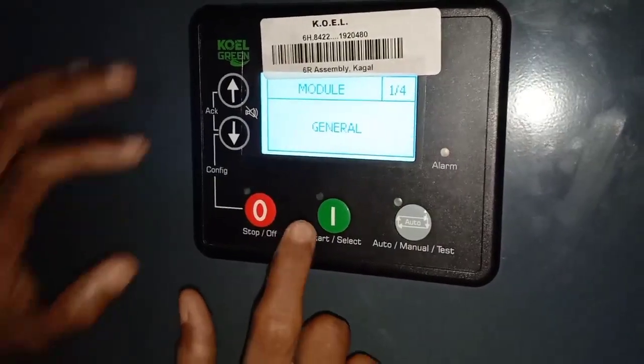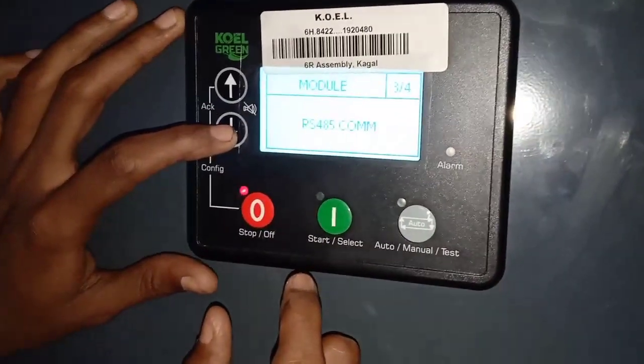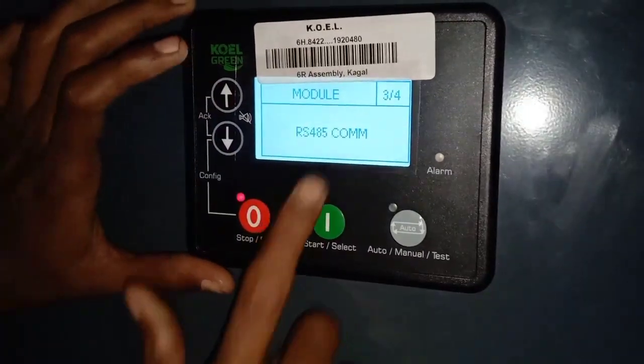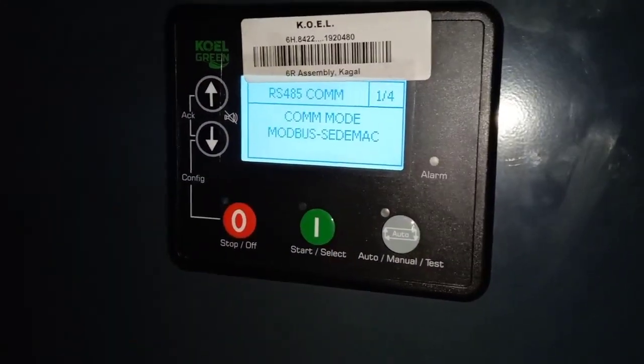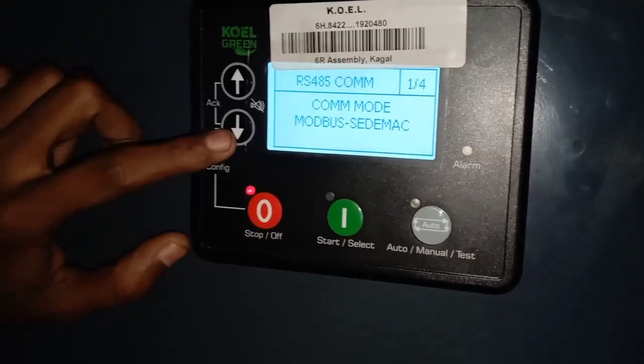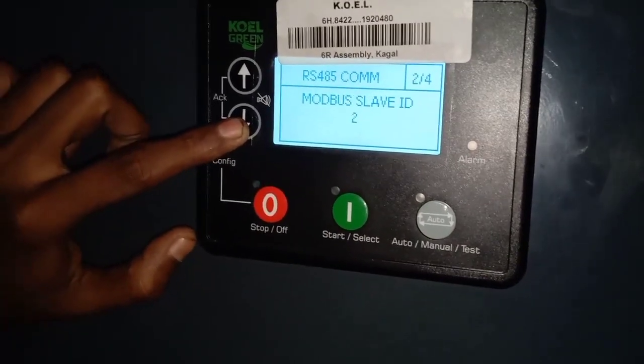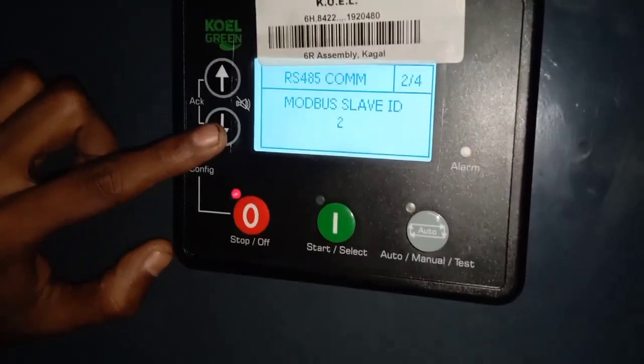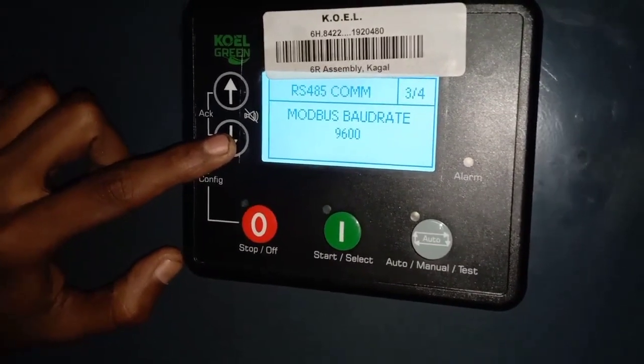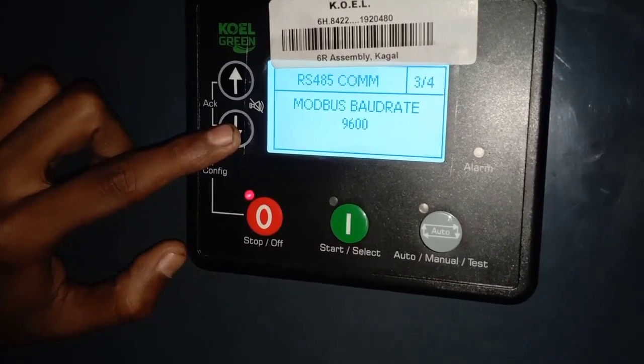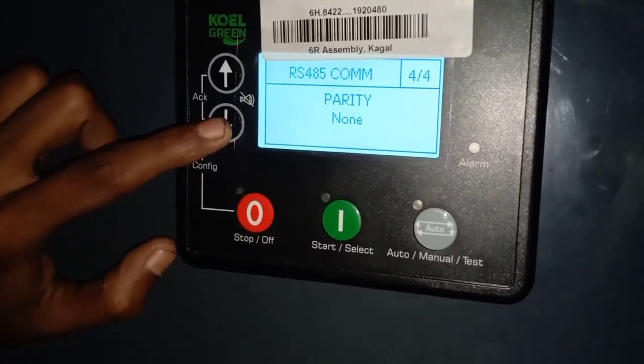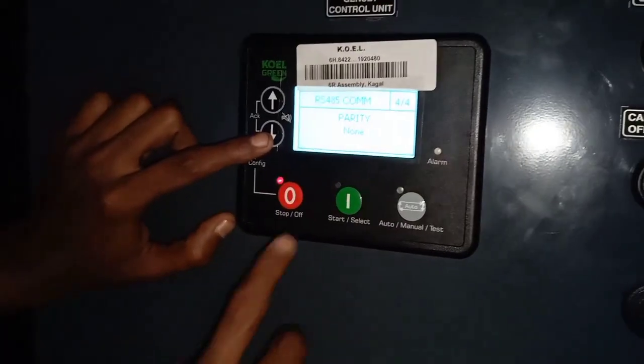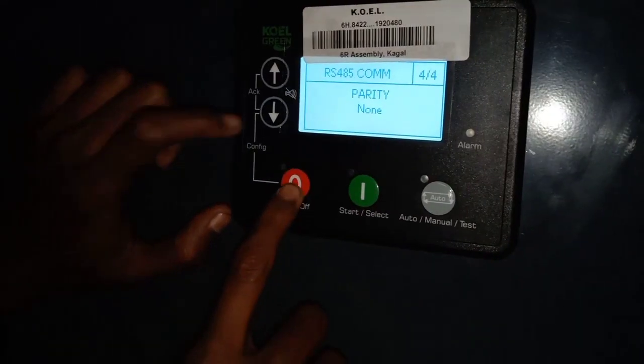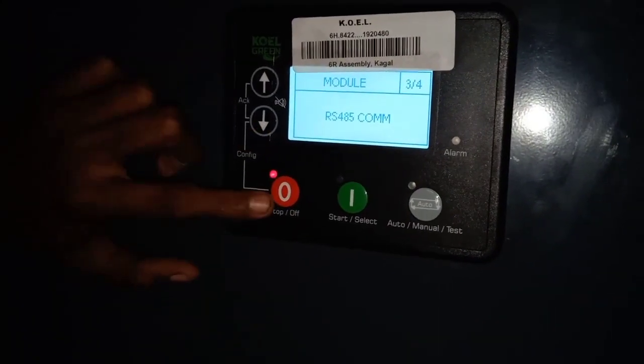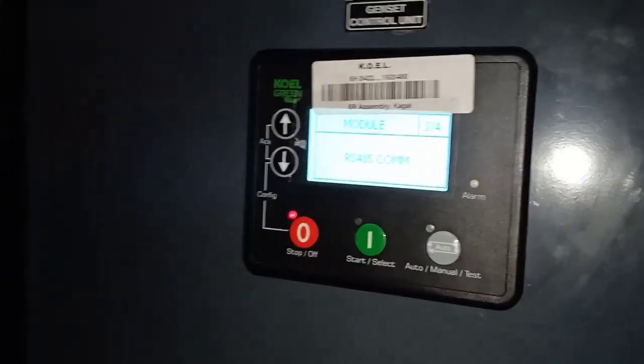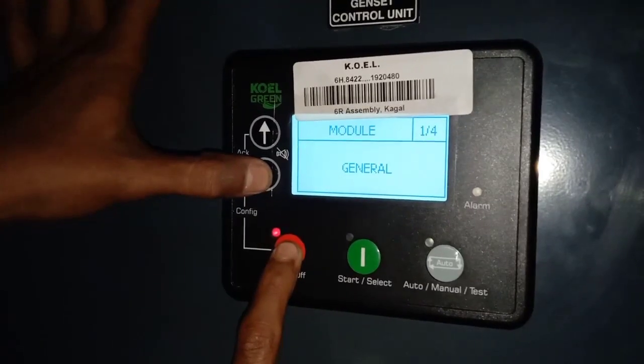Press the down key to select RS485 and press the start button to check settings. Now, please make sure Modbus is set to SEDEMAC. Press the down key once again and make sure the slave ID is set to number 2. Once again press the down key and make sure the Modbus baud rate is set to 9600. The last one is parity, and you should set it as none. Once all the above settings are checked and correct, press the stop button to go back to the menu. Now press and hold both the stop and down arrow keys to go to the main menu.